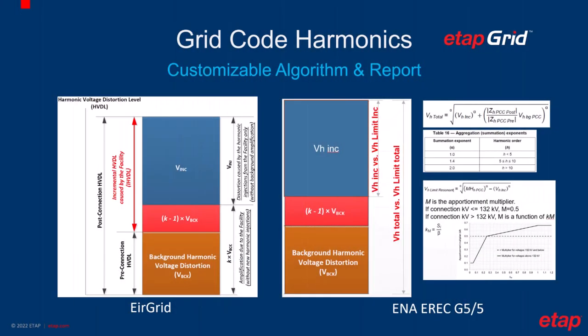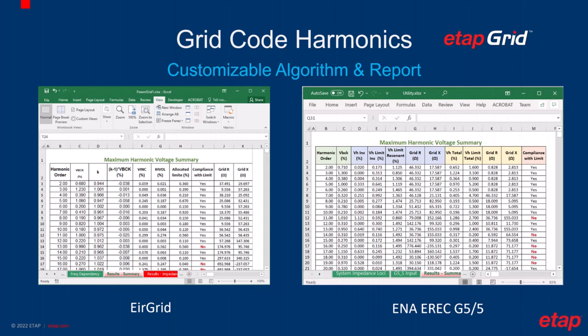One point worth mentioning is that different grid codes have different interpretations and different requirements of this type of analysis. One advantage of ETAP is that the basic calculation results are all saved in a SQLite database. If the grid code you need to work with has different factors to consider, different results to generate, or different formats of reports required, the modification can be done through Python scripts. The example here shows two grid codes with a similar concept but different calculation parameters and requirements. With a Python script, the report we showed you earlier can be modified to fit the new requirements with different calculation results. Please contact ETAP Help Center for detailed discussions.